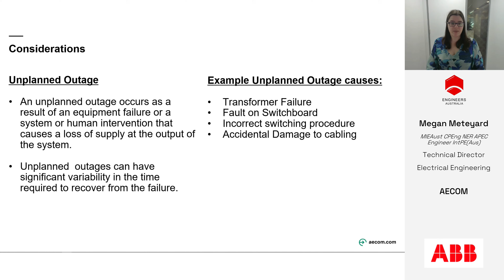So back to the project at hand. Knowing that the system, as shown there on the left, met the client criteria, there were then some discussions had in terms of those planning activities. Now, the project did specify withdrawable switchgear to enable maintenance to be carried out while the system is still operational. However, failure of the main switchboard or any of the UPS distribution boards, or even a through-life replacement of those switchboards in a planned scenario would mean that these elements were out of service without an alternative supply.